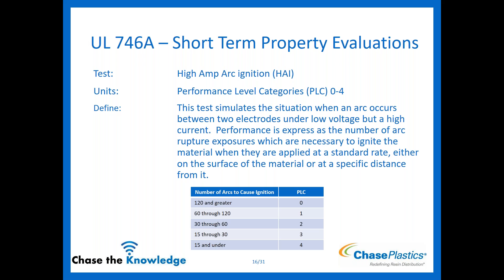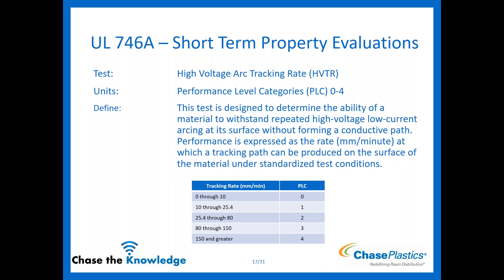HAI — High Amp Arc Ignition — is also on a PLC scale of zero to four. It simulates a situation where an arc occurs between two electrodes under low voltage but high current. This is given in the number of arcs it takes to cause ignition: 120 or greater arcs gives a PLC of zero, down to 15 or less giving a four. High Voltage Arc Tracking Rate is also a PLC rating of zero to four — it determines the ability to withstand repeated high voltage, low current arcing on the surface without creating a conductive path. This one is done in millimeters per minute: zero through 10 mm/min gives a zero, and 150 or greater gives a four.